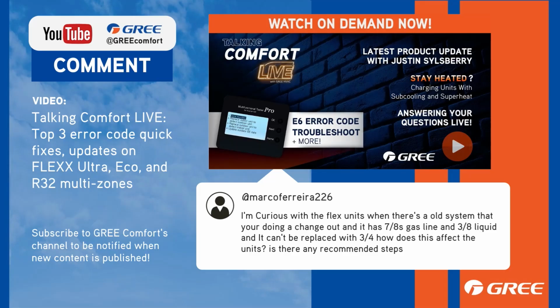From Marco: I'm curious with the FLEXX units, when there's an old system that you're doing a change out and it has 7/8 gas line and 3/8 liquid, and it can't be replaced with 3/4, how does this affect the units? Is there any recommended steps?